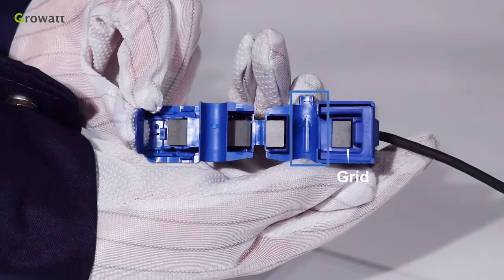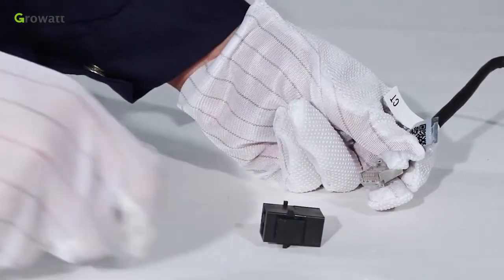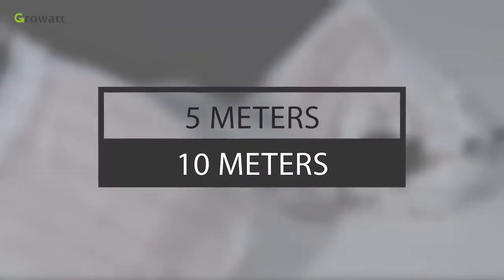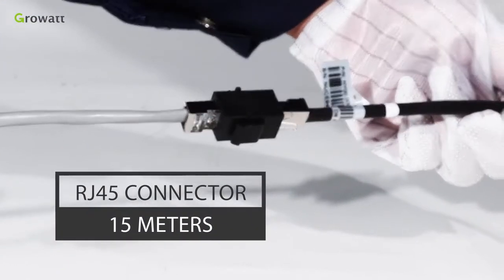Open the current transformer and you can see an arrow labeled on it which indicates the current direction. The direction of the arrow means current flows from the public grid to the user load. Growatt provides two cables whose lengths are 5 meters and 10 meters. Growatt also provides an RJ45 connector, so the total length can reach 15 meters.